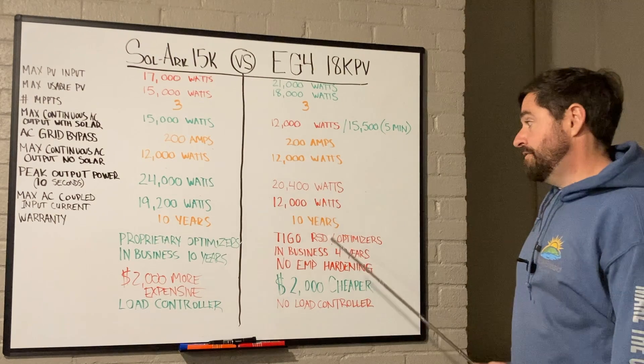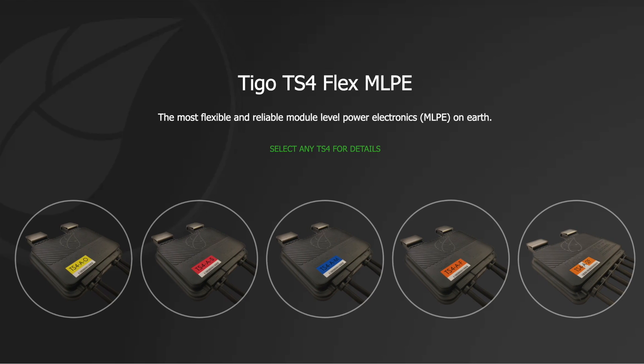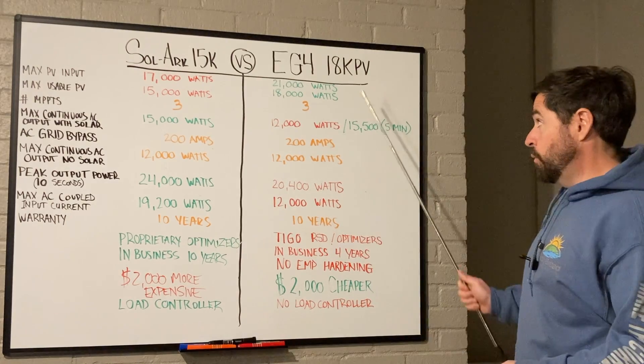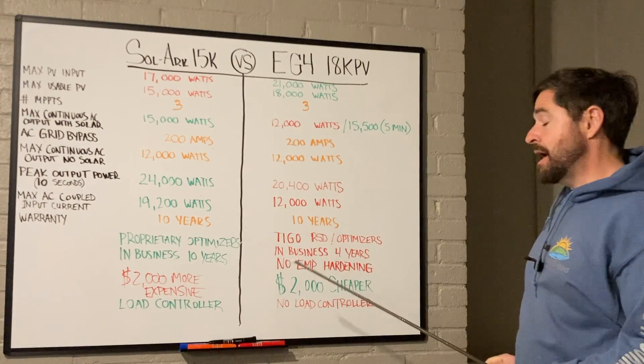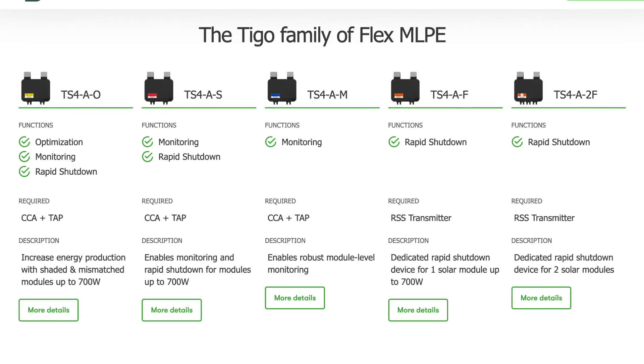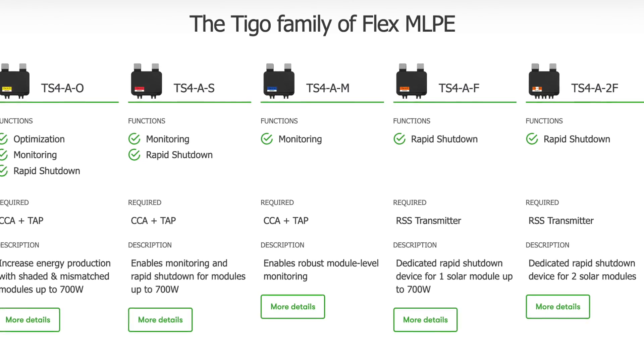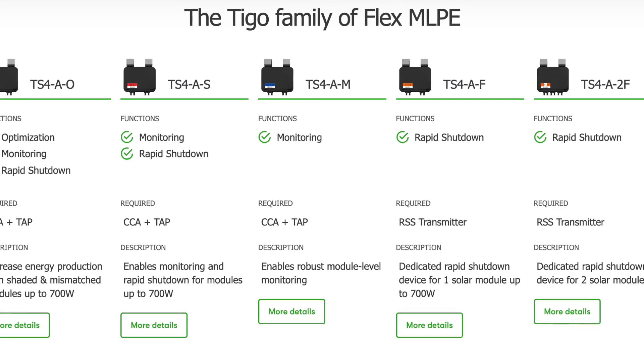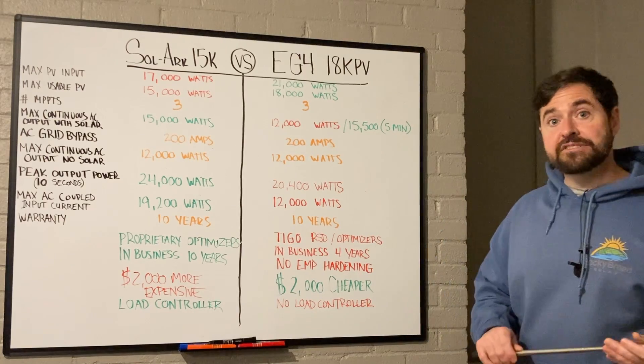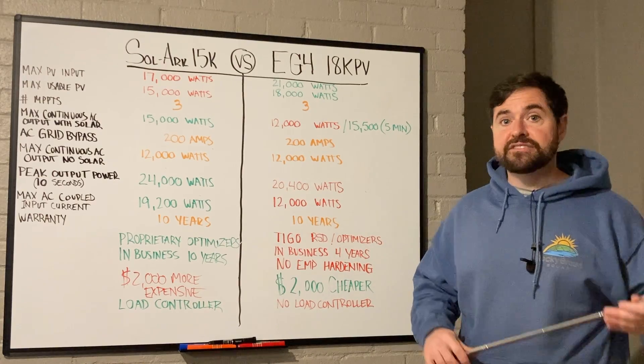With EG4, you'll need to go with Tigo optimizers. Neither of these inverters is rapid-shutdown compliant without optimizers — Sol-Ark's proprietary ones, or Tigo for EG4. With Tigo, you can choose just a rapid-shutdown compliant module to meet code, or an optimized module that helps with shading, module mismatch, or opposite-facing roof planes.